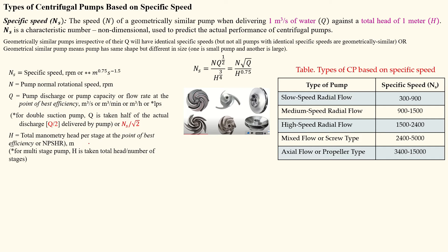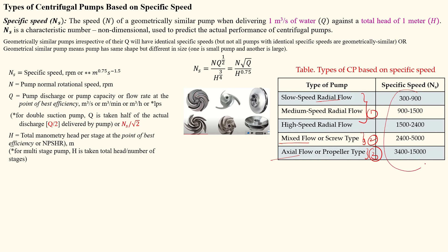For multi-stage pumps, the head per stage equals total head divided by the number of stages (number of impellers). Specific speed helps decide the characteristics curve and performance of the impeller. Based on performance and speed, pumps are classified as: slow speed radial flow, medium speed radial flow, high speed radial flow, mixed flow (screw flow), and axial flow — three broad categories: radial, mixed, and axial.